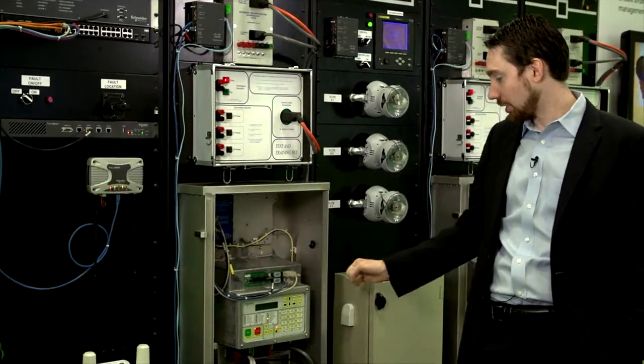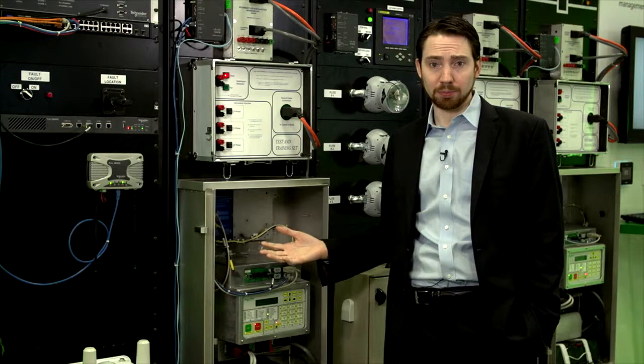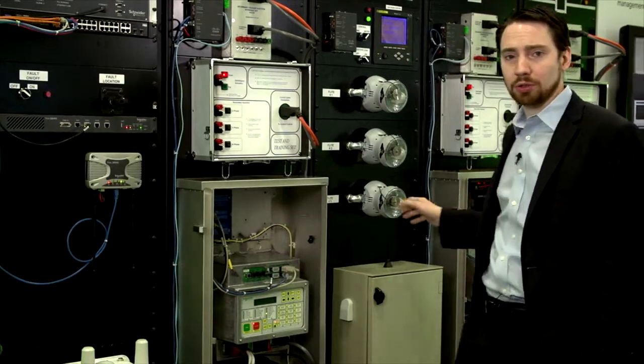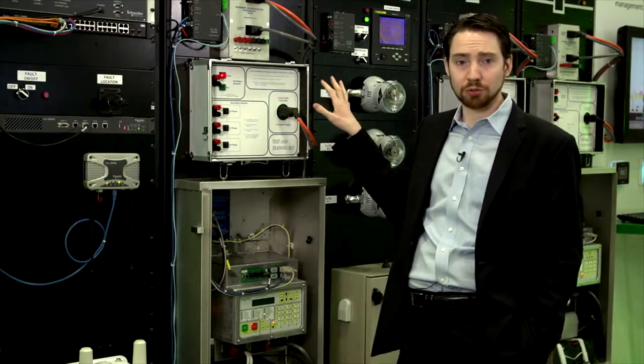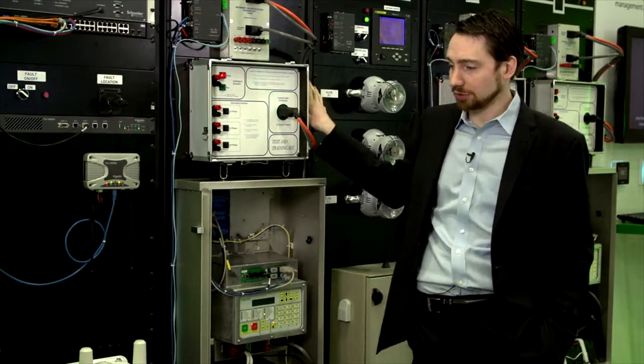This recloser is a smart device that can actually do its own loop automation. So we can communicate with other reclosers and different things in the circuit to be able to know how to automatically do FLISR, which is fault location, isolation, supply restoration.